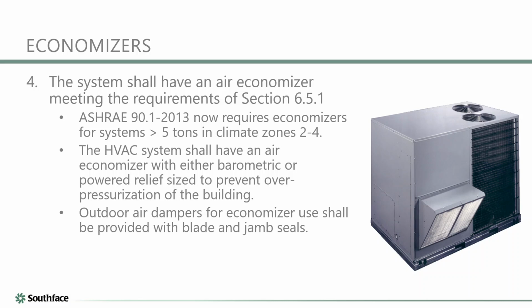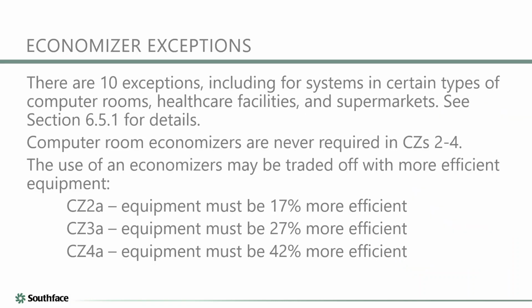There may be some ways and there may be some motivations for someone to essentially want to trade out of that economizer requirement, particularly if they think they're just not going to be able to get a lot of use and therefore a lot of efficiency or savings out of the equipment function. Yeah, that's a very good point, because this is a new requirement for this year. Some of our builders might not be used to using those economizers. So there is a bit of a carve out here, even within the simplified approach, that allows someone to basically install more efficient equipment. So I think that might be a path that a lot of our design folks in Georgia take.